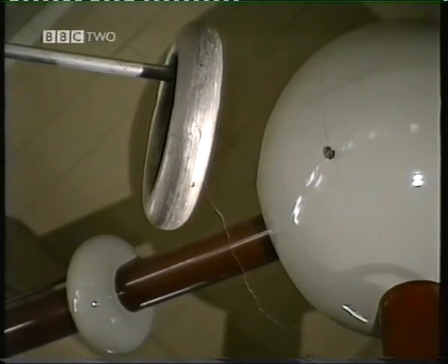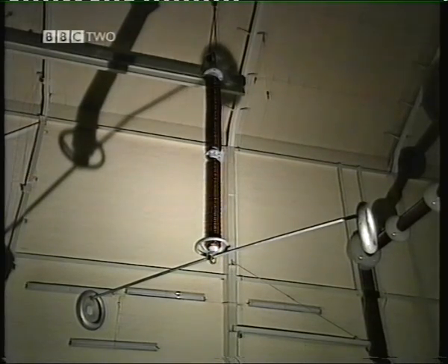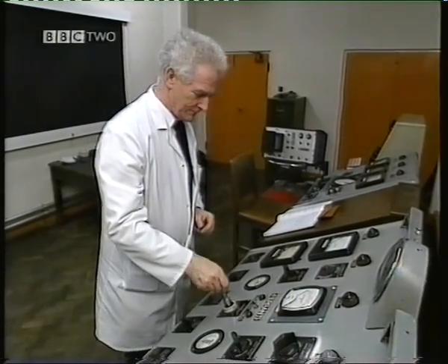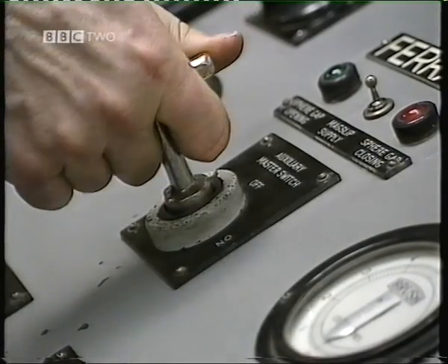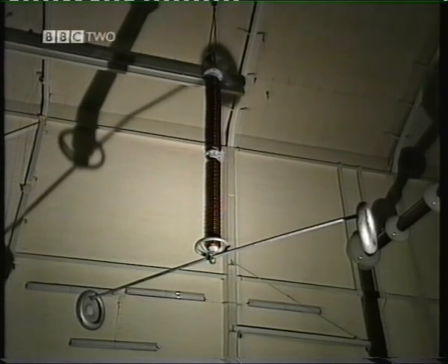A fine wire brings that potential down onto a conductor, or bus bar as it's called, which at the moment is suspended from the insulator under test. It's actually a post insulator, and it's over 4 meters in length. After allowing visitors to make a safe exit, the high tension is switched on.